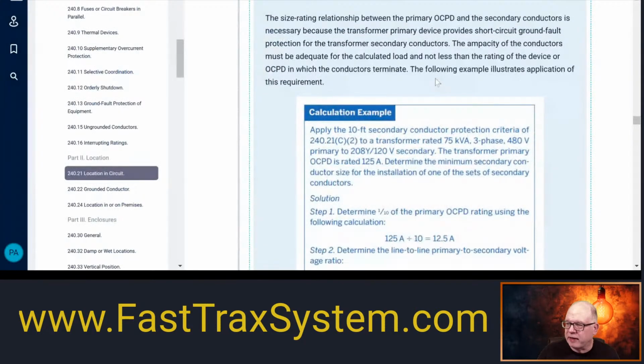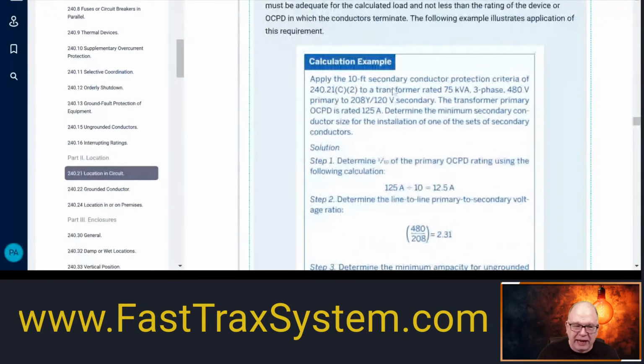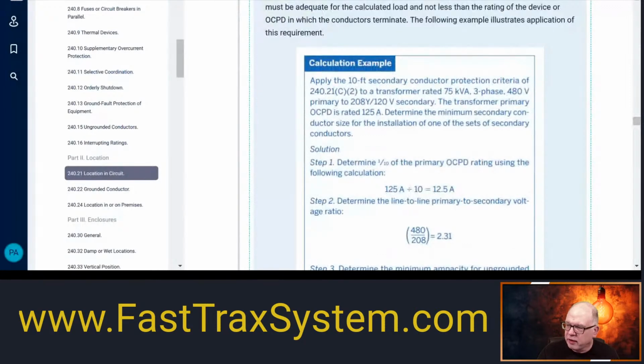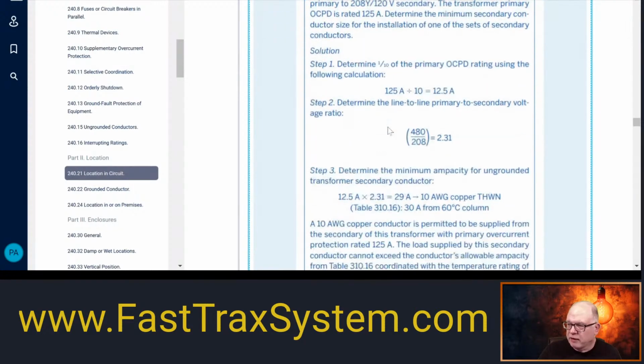All right, so let's look at this example. What do we got here? Let's say we're going to apply the 10-foot secondary conductor protection criteria, which is 240.21(C)(2). We're going to do this for a 75 kVA transformer, 3-phase, 480 volt primary, 208Y/120 secondary. Very common application, and a very common transformer, 75 kVA. It says the transformer primary overcurrent device is 125 amps. So it's already done the math and telling us what the primary is. Now what we have to determine is the minimum secondary conductor size for the installation of one of the sets of secondary conductors.